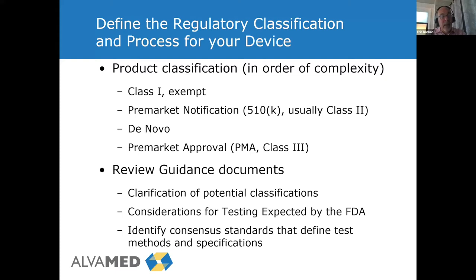And finally, there's pre-market approval. These are class three products. They take a long time, and they always need clinical data. This is generally a multi-year process with the agency. Once you file the PMA, it's generally a year or so of review with the FDA.